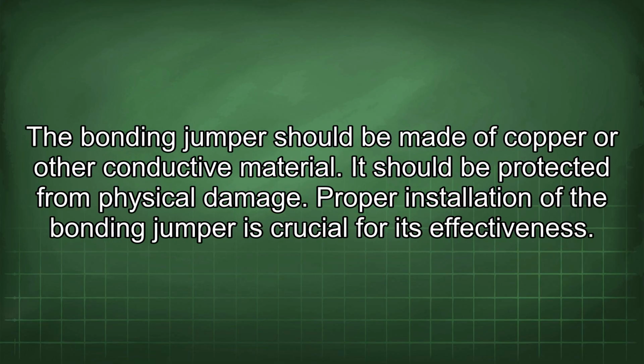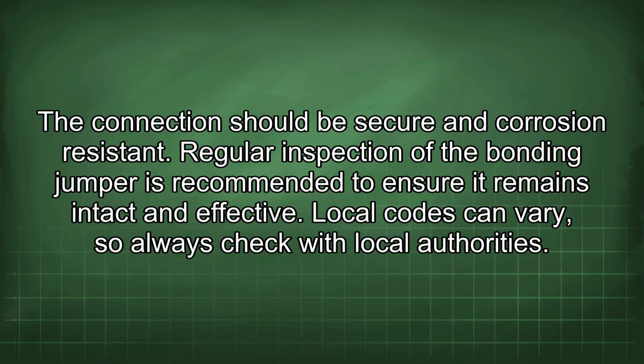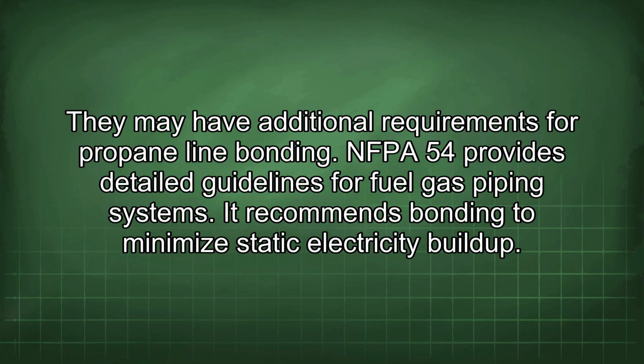The bonding jumper should be made of copper or other conductive material. It should be protected from physical damage. Proper installation of the bonding jumper is crucial for its effectiveness. The connection should be secure and corrosion resistant. Regular inspection of the bonding jumper is recommended to ensure it remains intact and effective. Local codes can vary, so always check with local authorities. They may have additional requirements for propane line bonding.